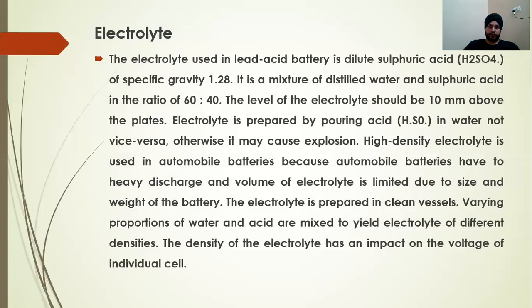When water evaporates from the electrolyte solution, the quantity of water decreases and the concentration of sulfuric acid increases. This increases the density. If the ratio is not proper, the chemical reaction will not occur properly, and the battery's voltage and power output will decrease. The efficiency of the battery depends on maintaining the correct electrolyte concentration.